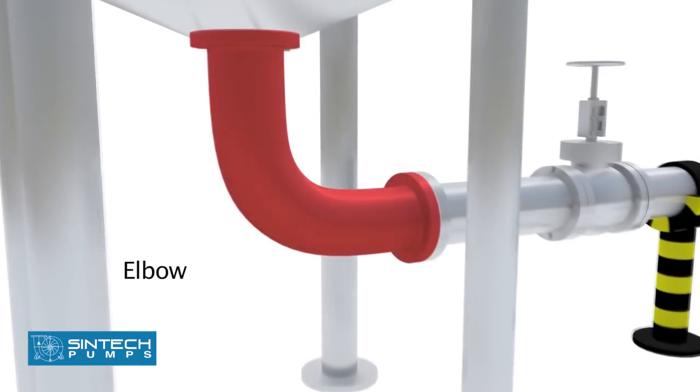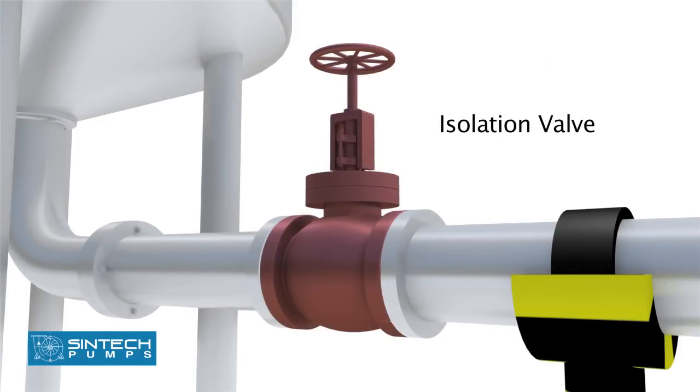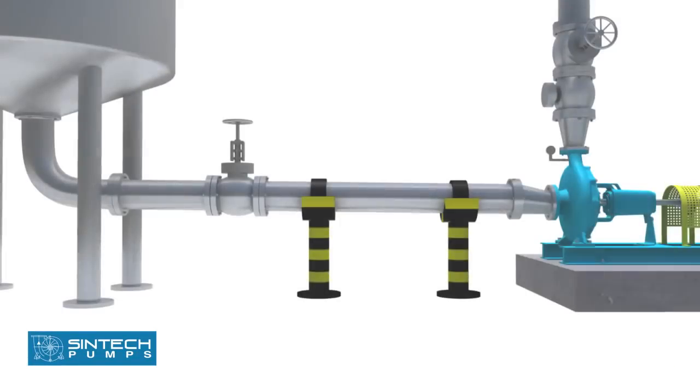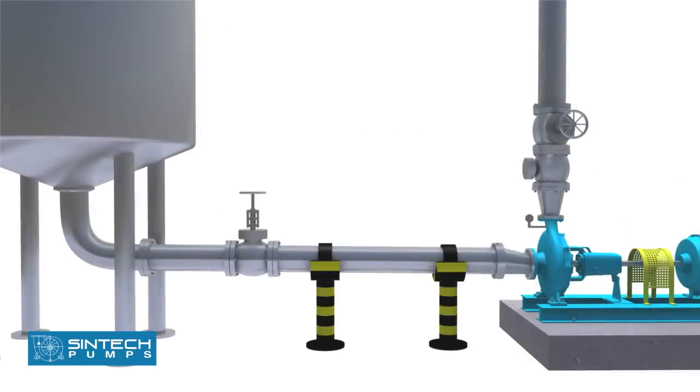The elbow should be of standard type or of the long radius type. Isolation valve should be provided in suction line. The pipe supplying from the tank into the pump should have a descending inclination. The straight run of the piping leading to the pump suction nozzle should be at least 3 times to 6 times the diameter of the pipe from the upstream elbow.